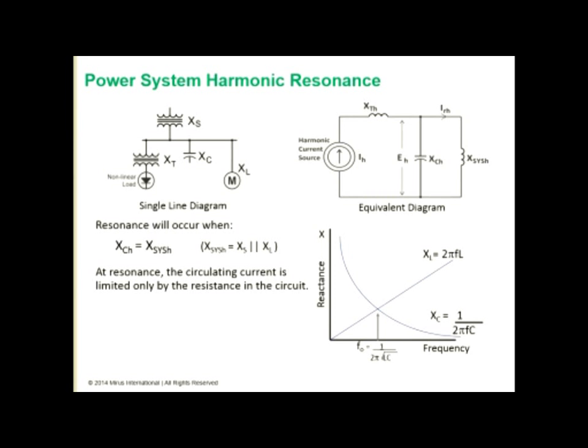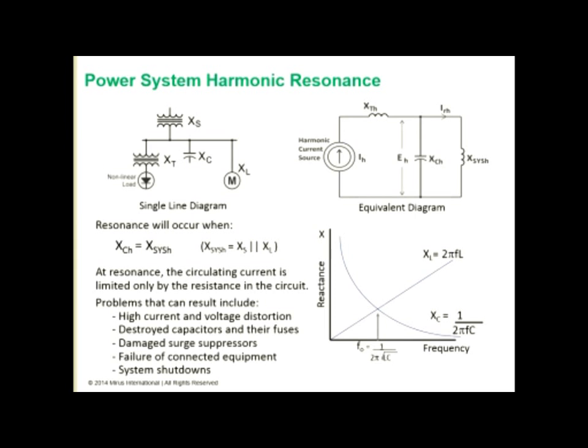If that particular resonance frequency happens to be at a harmonic that is common on the power system, generated by our nonlinear loads, then we can create conditions where we'll get a lot of circulating current between the power factor correction capacitors and the other loads in the system. The circulating current will produce more voltage drop across here, and that voltage drop appears as a harmonic voltage that will drive more current through the system, and it'll continue to increase, basically limited by the resistance in the system. And so the result can be very high levels of current and voltage distortion.